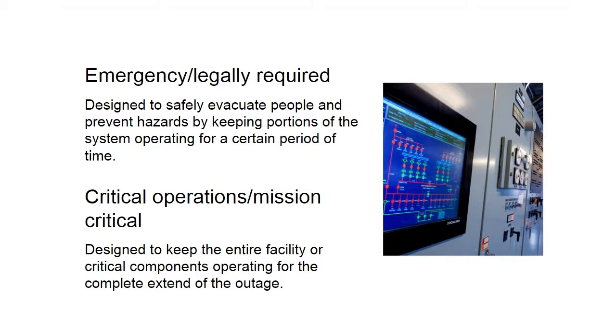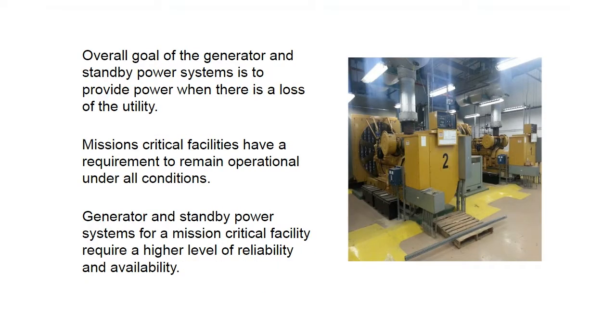Critical operations center, these are business continuity type functions, as Ken went into detail on, and the desire to keep that system or that entire facility up and running in the event of an extended outage so that from a business continuity standpoint, things continue to operate and function as they would in any normal condition. The overarching goal here, obviously, is that the generator and the standby power systems are to provide power when there's a loss of utility.